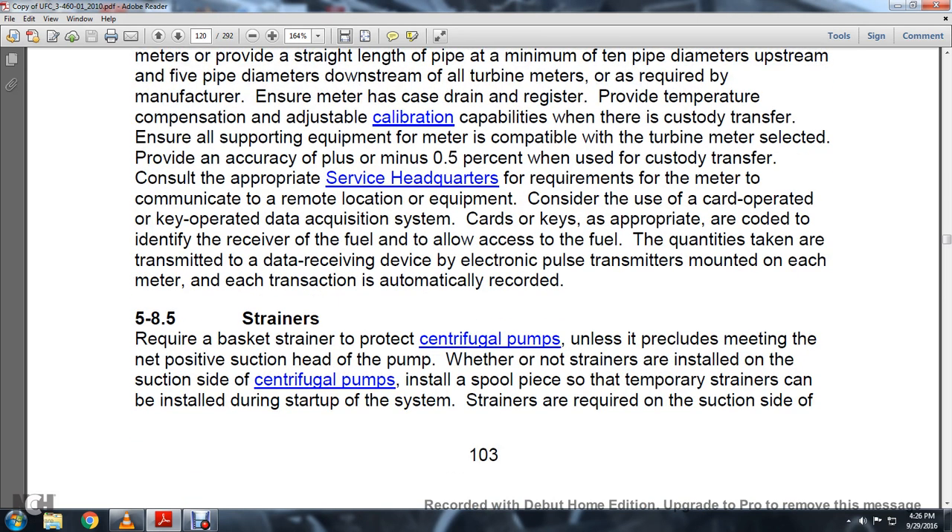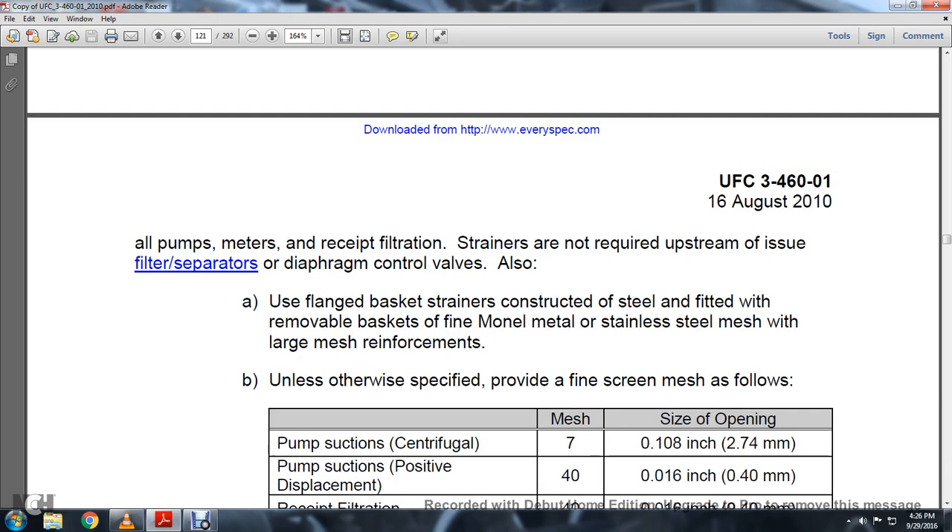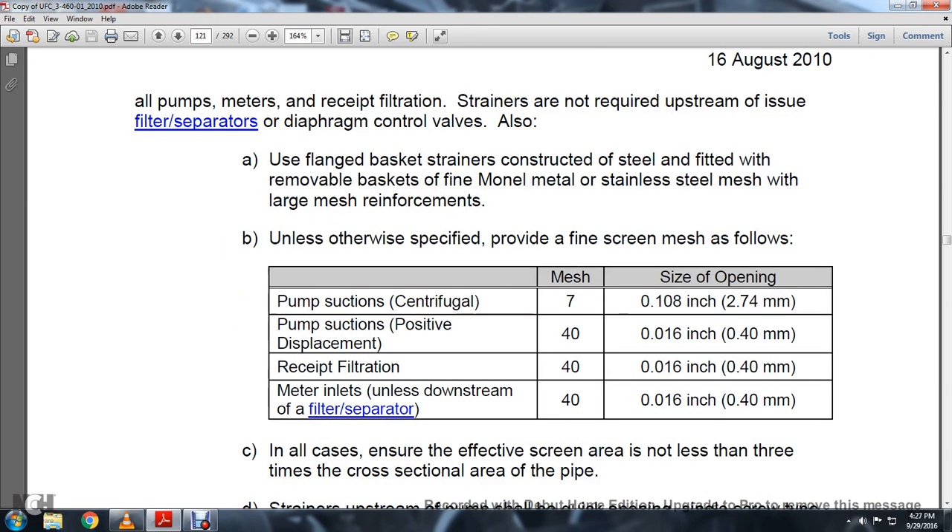Section 5.8.5 Strainers: Require a basket strainer to protect centrifugal pumps unless it precludes meeting the net positive suction head. Whether or not strainers are installed on the suction side of centrifugal pumps, install spool pieces where temporary strainers can be installed during start-up. Strainers are required on the suction side of all pumps, meters, and receipt filtration. Use flange basket strainers constructed of steel with a removable basket of fine Monel metal or stainless steel mesh and a large mesh for reinforcement unless otherwise specified.